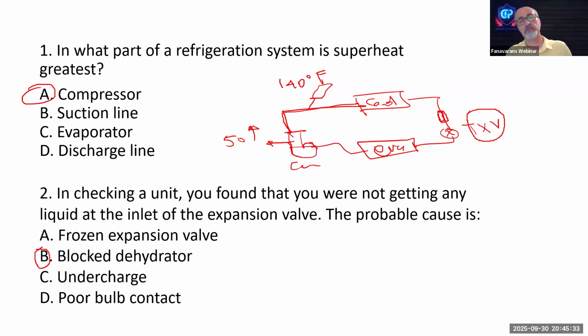So as a technician, when you do a service call and you see the problem, the question is, how do you find out if this filter is blocked? You need to check the temperature before and after the filter dryer. If you have more than 3 degrees Fahrenheit difference, the filter dryer needs to be replaced. So B is the answer, blocked dehydrator or filter dryer. I haven't seen any book that calls the filter dryer a dehydrator. They call it filter dryer. But in CFQ questions, you see lots of words like this, and you need to get familiar with these kinds of words.